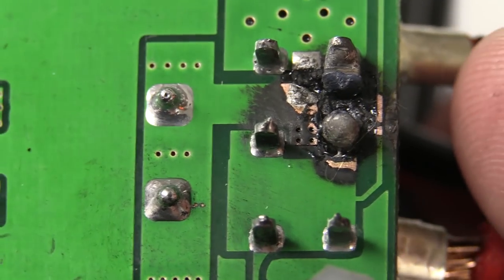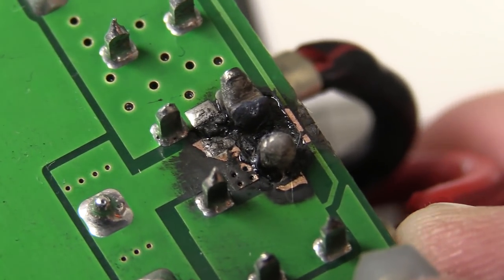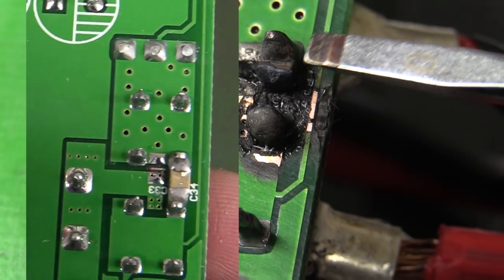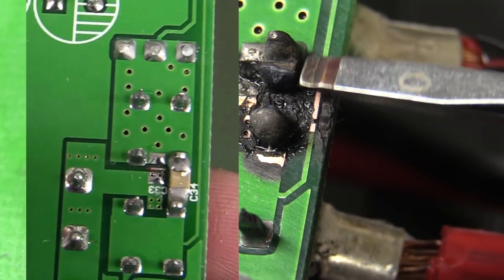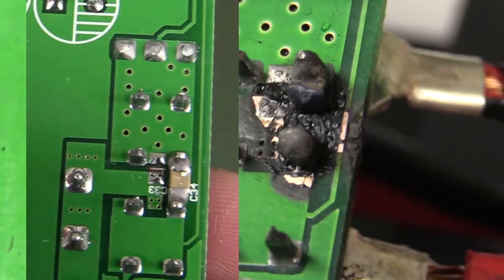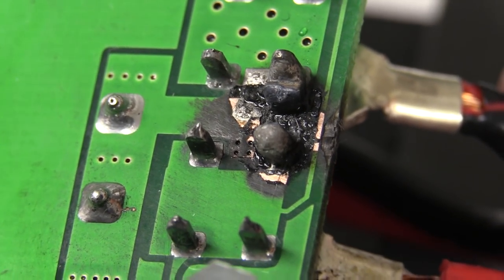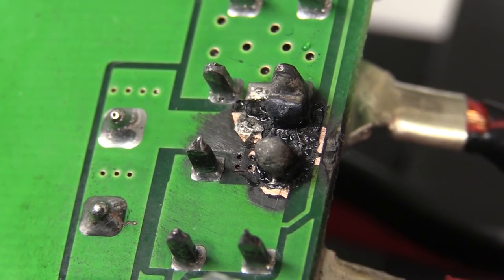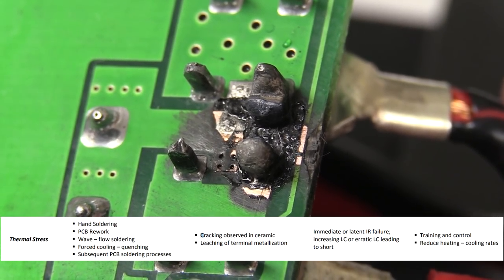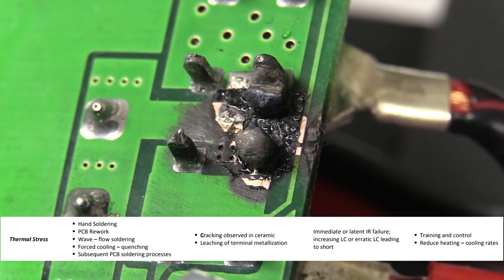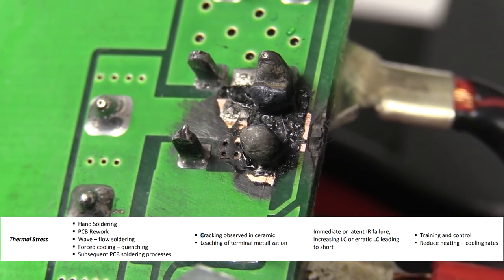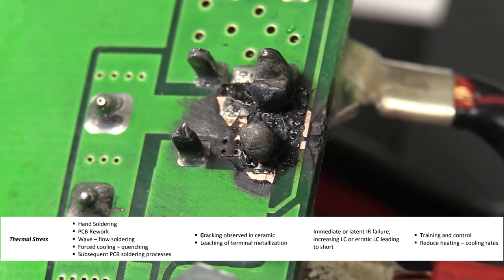That's probably why the other one wasn't fitted. Would be my guess. But, yeah. So it could have done some damage to the cap, which then caused premature failure. Even if it was spec'd correctly.